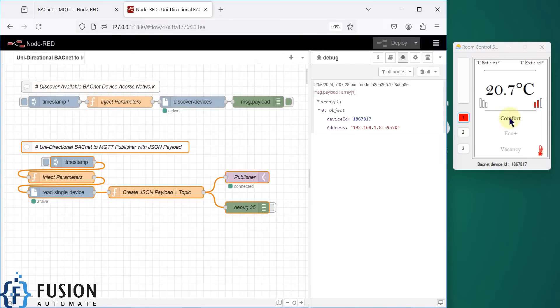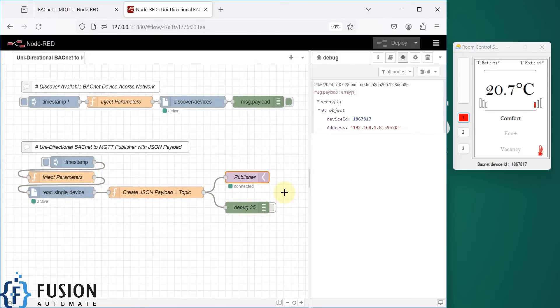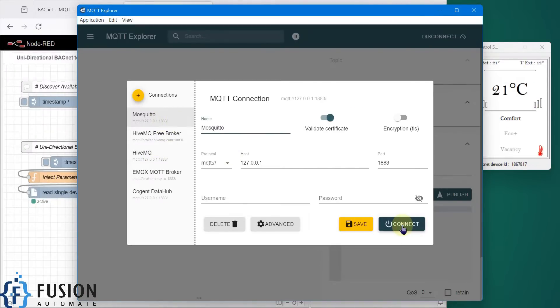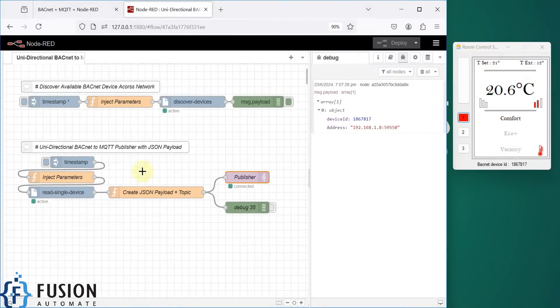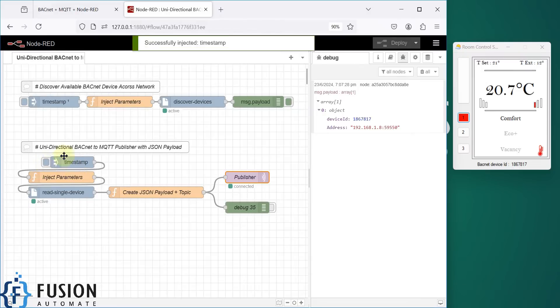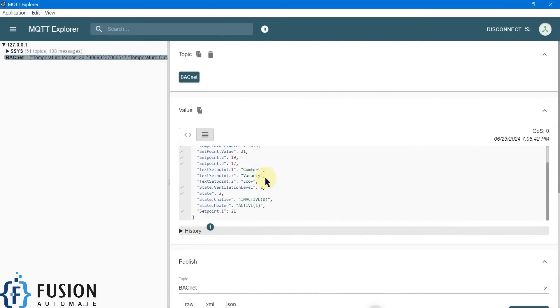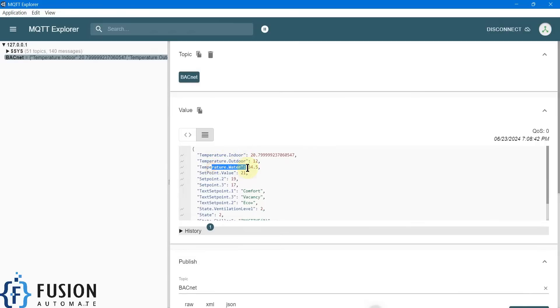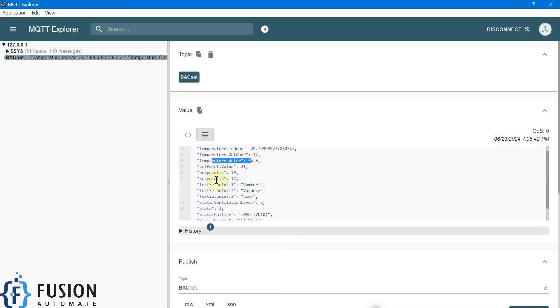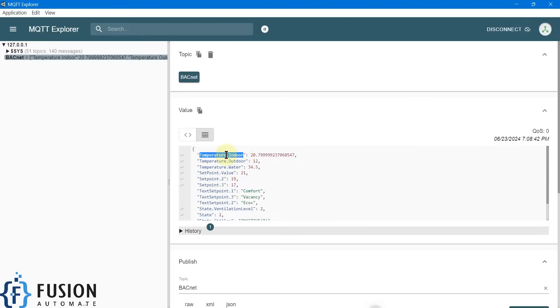This set of nodes has successfully executed and found the room controller simulator. Now we can use the second section to read data from this simulated device and publish it to the MQTT broker. The MQTT broker is my own Mosquitto instance running locally. We can launch MQTT Explorer software to see the data, and I've connected to the Mosquitto broker. After injecting the timestamp node, you can see a BACnet topic containing data like temperature, indoor temperature, outdoor temperature, hot water, setpoint, and everything.